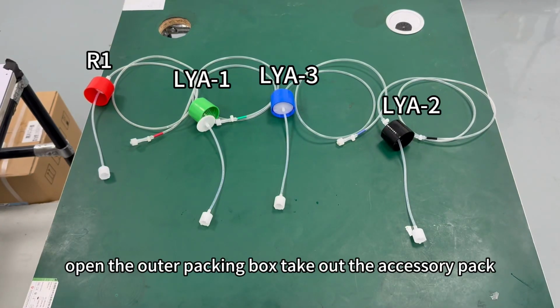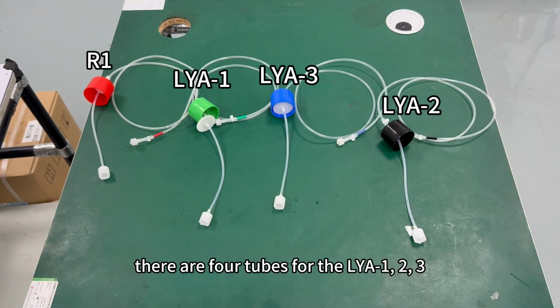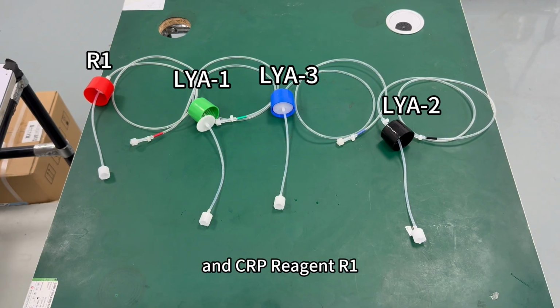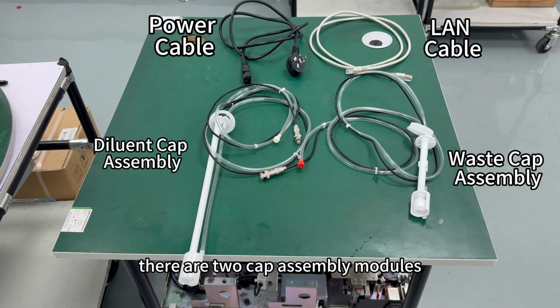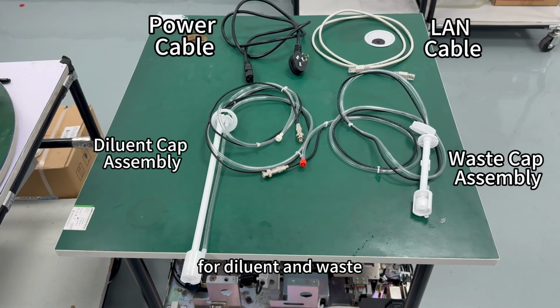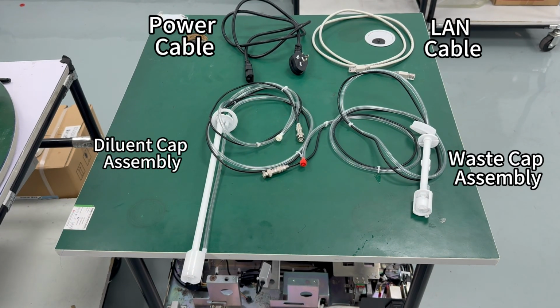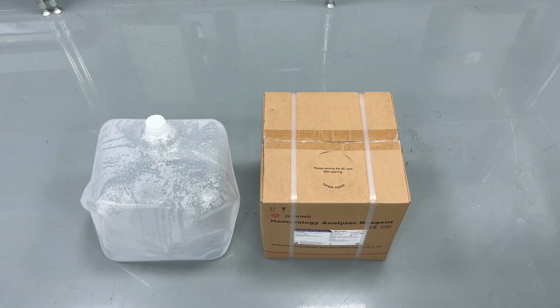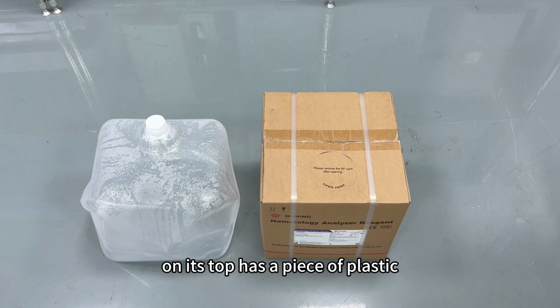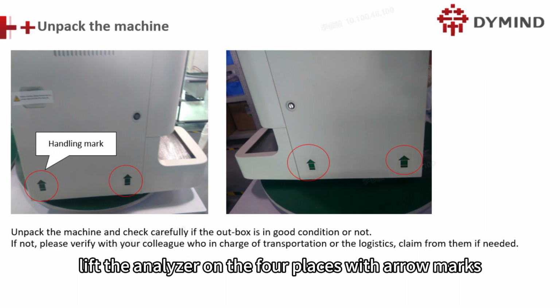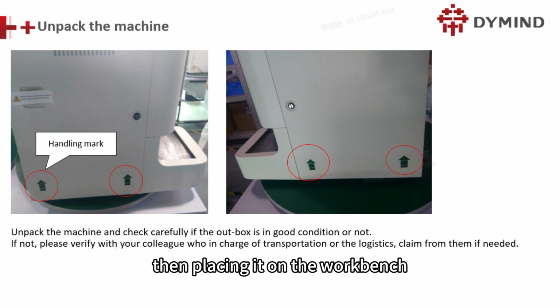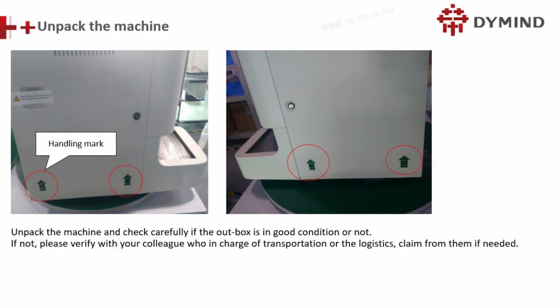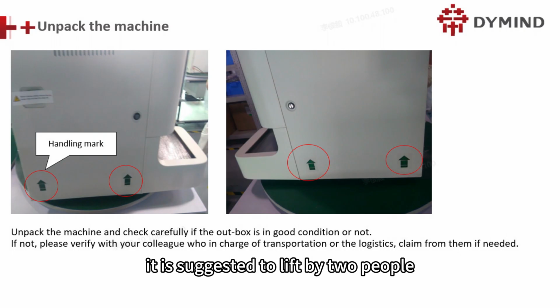Open the outer packing box and take out the accessory pack. There are 4 tubes for the LYA1, 2, 3, and CRP reagent R1. There are 2 cap assembly modules for diluent and waste. The power cable and the LAN cable. The waste tank, and the diluent package, which on its top has a piece of plastic to fix the tank's bottleneck. Lift the analyzer at the 4 places with arrow marks, then place it on the workbench. It is suggested to lift it with 2 people.